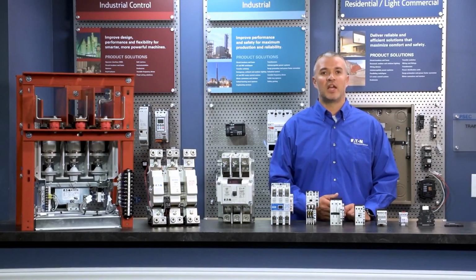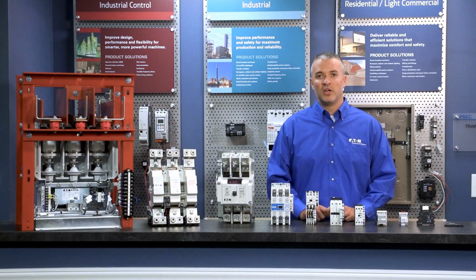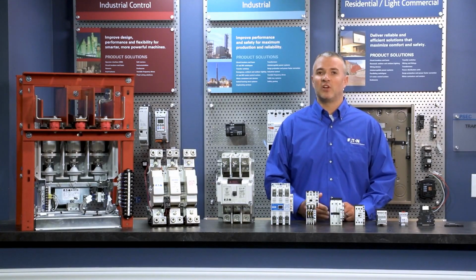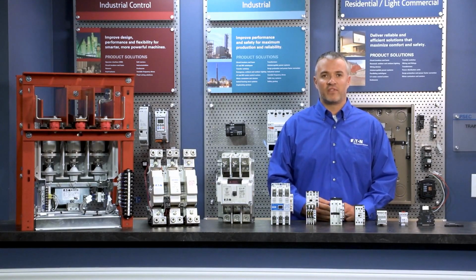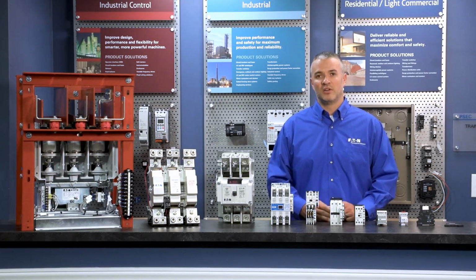In nearly every case, the only information that is needed is the motor's horsepower and voltage. NEMA contactors or starters come in a range of sizes from size double-aught to size 9, and for reference, a size double-aught contactor has a maximum horsepower rating of 2 horsepower at 460 volts, and a size 9 contactor has a rating of 1600 horsepower. You will probably never see anything larger than a size 6 except for very unusual applications.